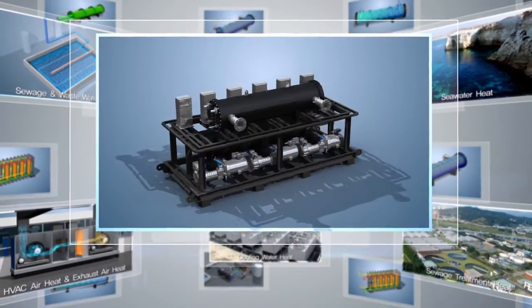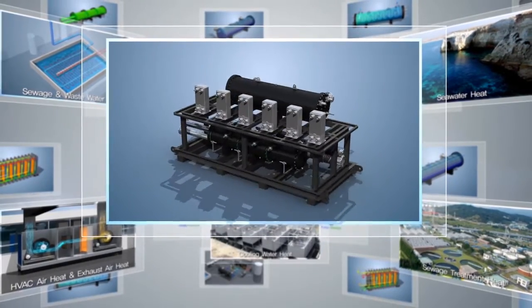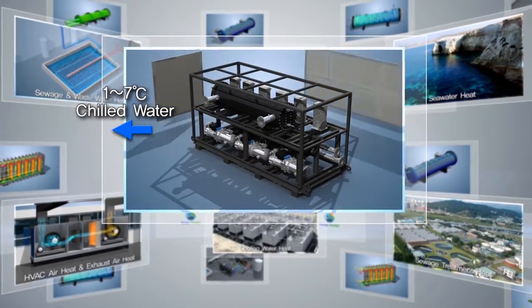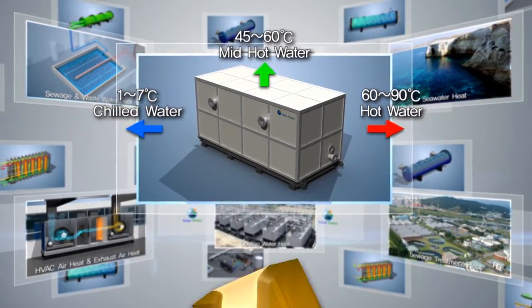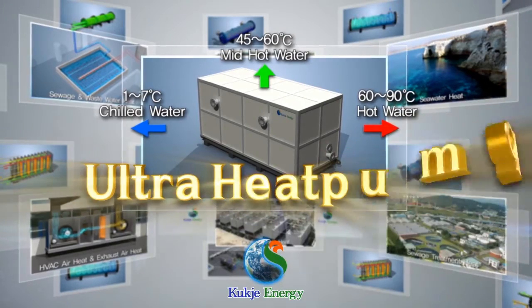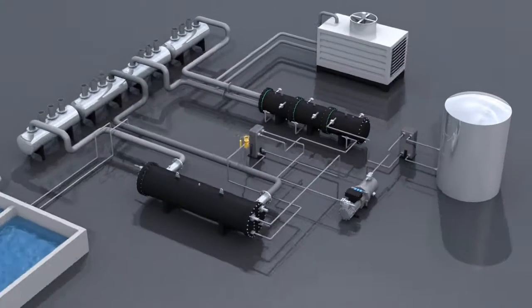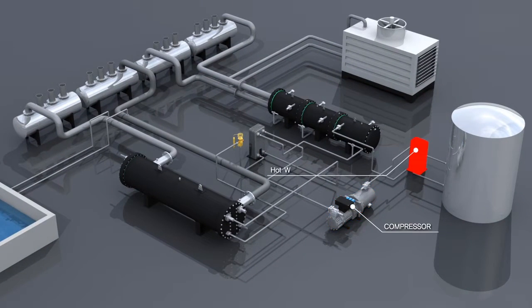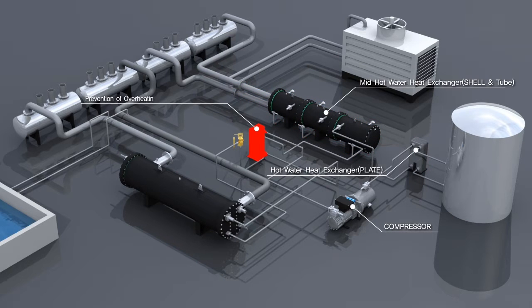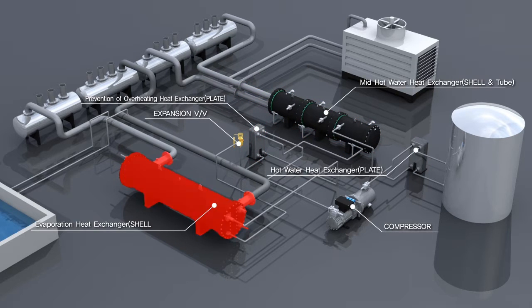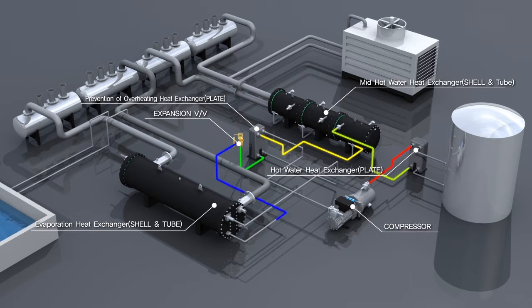Ultra heat pump is a high technological energy recycling system. It can simultaneously produce chilled water from 1 to 7 degrees Celsius, mid-hot water from 45 to 60 degrees Celsius, and hot water from 60 to 90 degrees Celsius by utilizing collected multiple heat sources in the Earth. Ultra heat pump basically consists of compressor, condenser, expansion valve, and evaporator. Within this cycle, ultra heat pump is precisely designed to produce chilled and hot water at the same time, while maintaining heat balance according to load fluctuation.